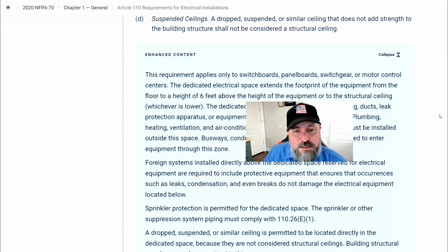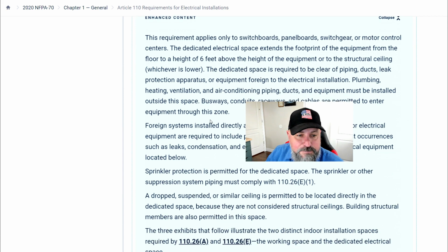The dedicated electrical space extends the footprint of the equipment from the floor to a height of 6 feet above the height of the equipment or to the structural ceiling, whichever is lower. The dedicated space is required to be clear of piping, ducts, leak protection apparatus, or equipment foreign to the electrical installation. Plumbing, heating, ventilation, and air conditioning pipes, ducts, and equipment must be installed outside the space. Busway, conduits, raceways, and cables are permitted to enter the equipment through this zone because they're electrically related.